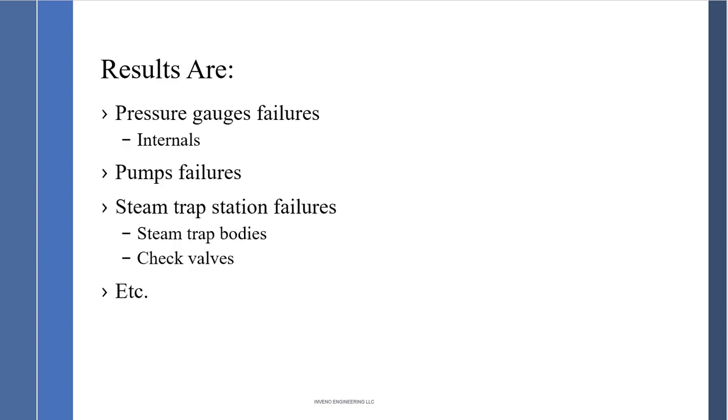Pressure gauge failures, internals failing, pump failures, condensate pump failures, steam trap station failures. Steam trap bodies failed, check valves. There is no steam trap that can withstand water hammer. So therefore, we have to eliminate. A root cause analysis, one of the biggest things that cause steam trap failure is water hammer.